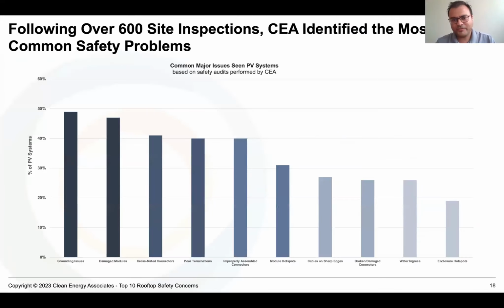I'd like to do a deep dive into the common issues we find on sites. We've found issues like grounding problems, damaged modules, issues with connectors, broken connectors, cross-mated connectors, connectors not assembled properly, cables on sharp edges, hotspots on modules, and issues inside enclosures like water ingress and splices that aren't up to standard.